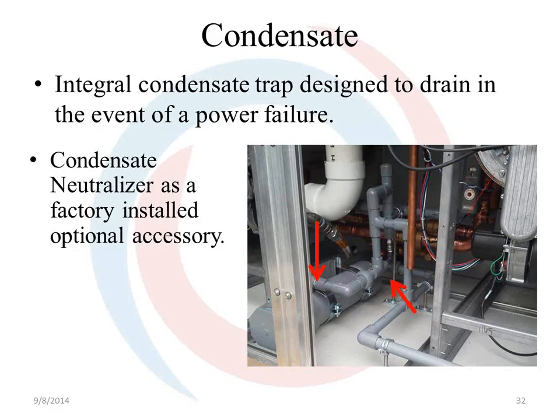There's a condensate neutralizer. That's this cylinder down here. And the inlet is on the top of the neutralizer and the outlet is on the bottom. In the event of a power failure, the majority of the condensate will drain out. The remaining condensate has plenty of room to expand, so freezing will not break the neutralizer. Once the unit regains power, that 90-degree condensate will quickly melt any frozen condensate in the neutralizer. Now, this condensate neutralizer is an option. Not every code municipality does require it.